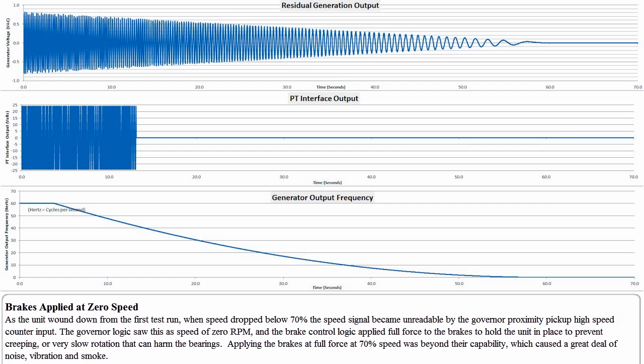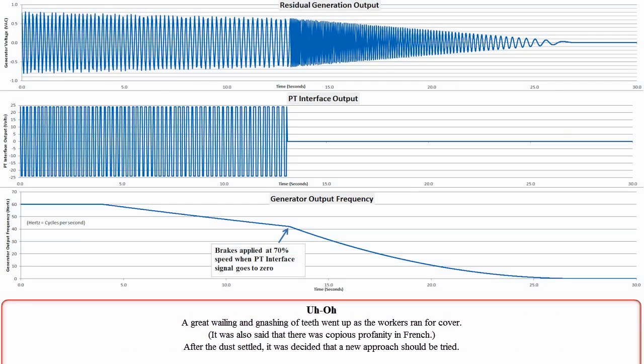As the unit wound down from the first test run, when speed dropped below 70%, the speed signal became unreadable by the governor proximity pickup high-speed counter input. The governor logic saw this as speed of 0 RPM, and the brake control logic applied full force to the brakes to hold the unit in place to prevent creeping, or very slow rotation that can harm the bearings. Applying the brakes at full force at 70% speed was beyond their capability, which caused a great deal of noise, vibration, and smoke. A great wailing and gnashing of teeth went up as the workers ran for cover. It was also said that there was copious profanity in French.